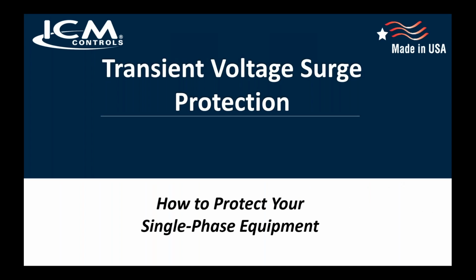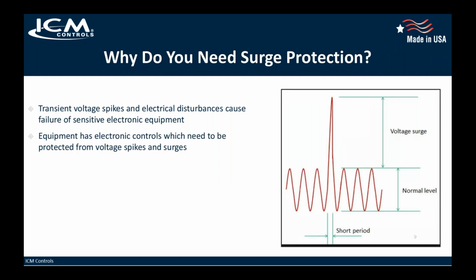Now we'll talk a little bit about voltage surge. Voltage surge is different than a voltage rise. Over and under voltage, as far as relation to grid power changes, are totally different than transient voltage surges, and we'll explain that a little bit. So you can see in this diagram, transient voltage surges are a spike outside of the normal level of your sine wave. What that means is your AC voltage is coming in at a normal nominal level, and then all of a sudden, in a very short period of time, you get a huge spike. These are fast-acting transient voltage surges, and they are very detrimental to sensitive equipment, especially in mini splits, as we'll talk about a little bit later. Electronic equipment that has boards in it is going to need some type of protection against these spikes.